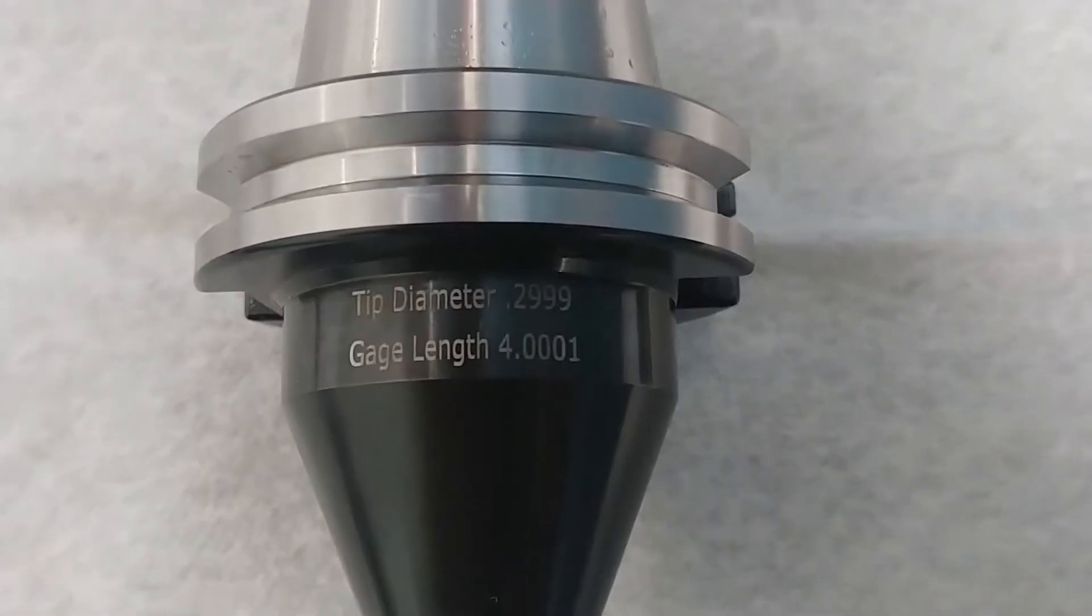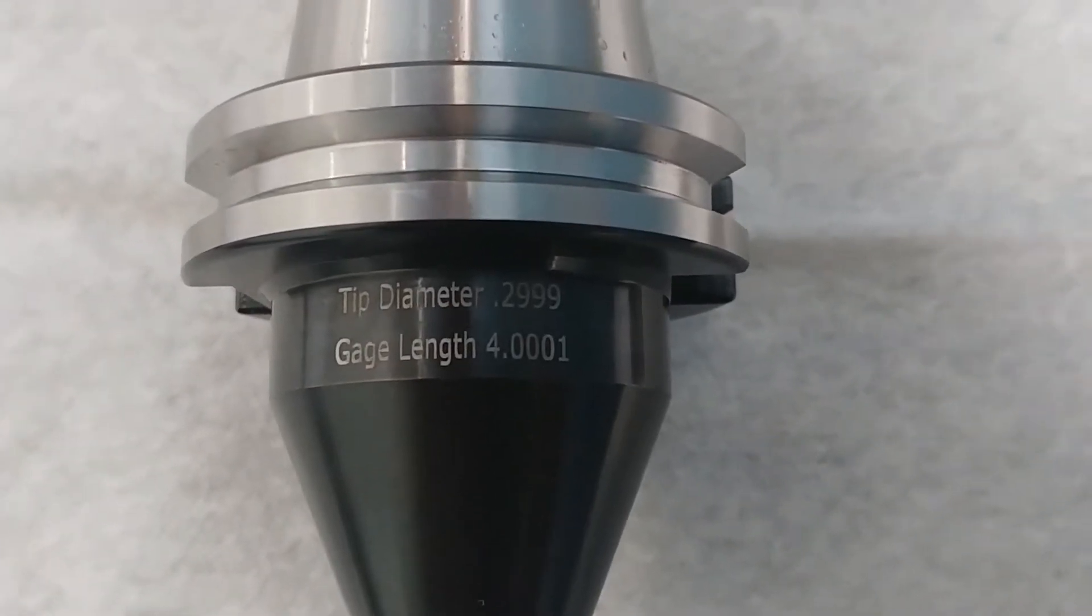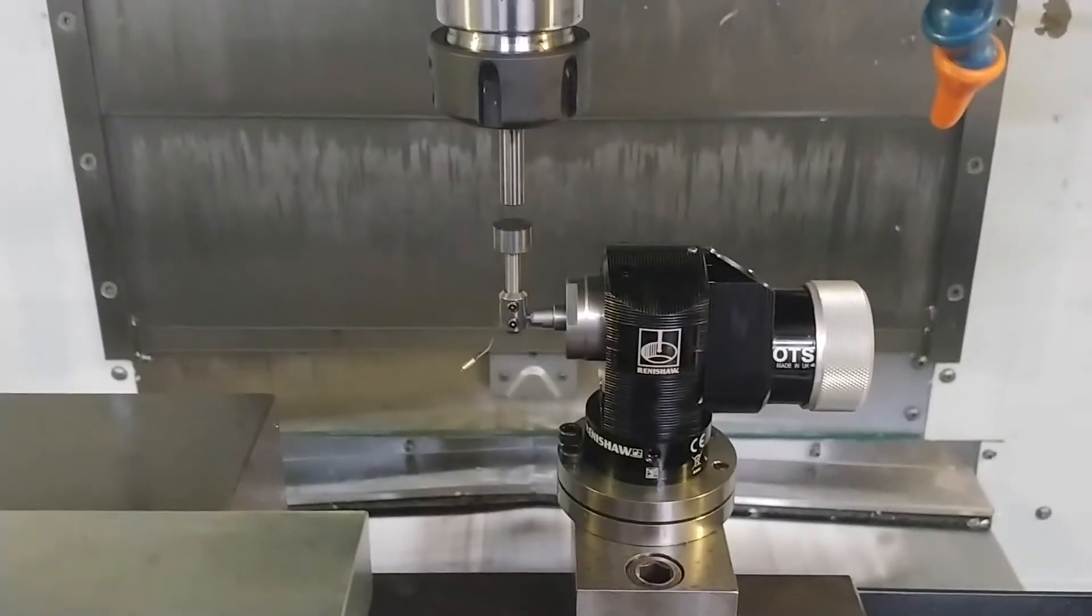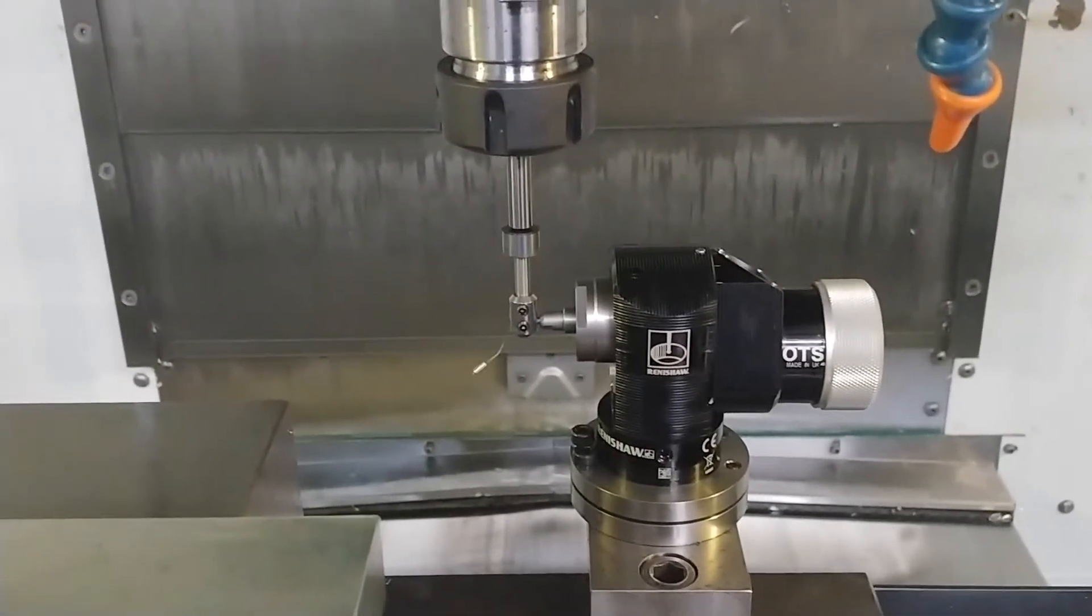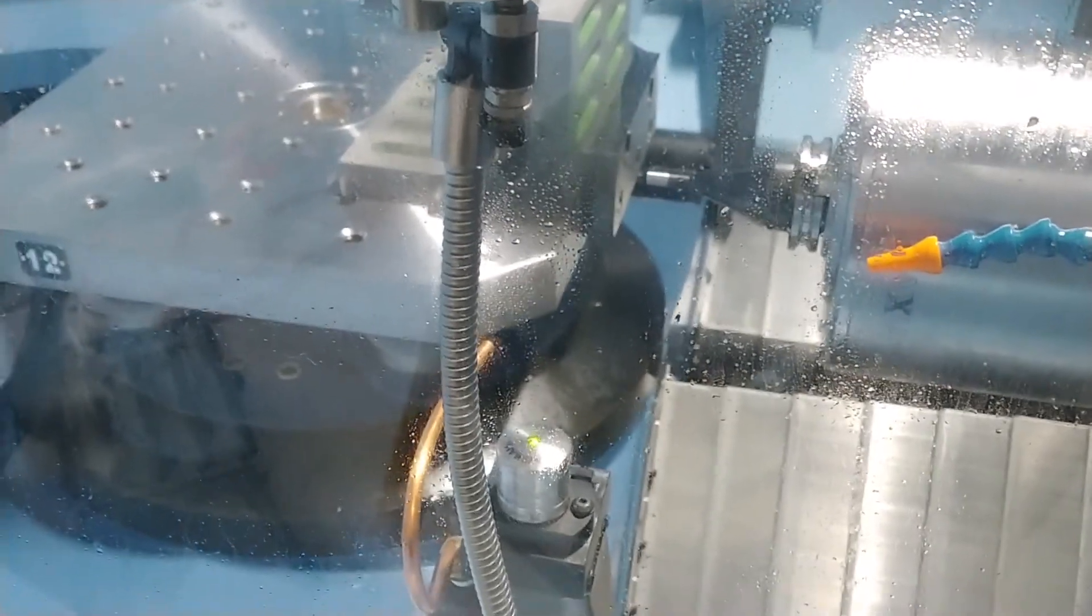Obtain a master tool and a gauge block. A master tool has a known tool length from the spindle taper gauge line and a known diameter. If your machine has a touch tool setter or a laser tool setter, it is important to calibrate the probe with the same master tool used to calibrate the tool setter.